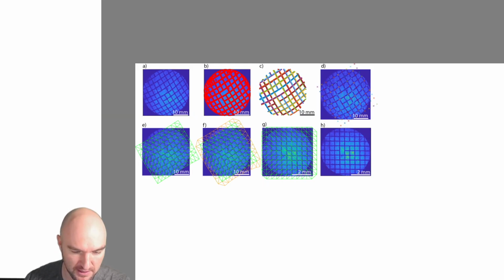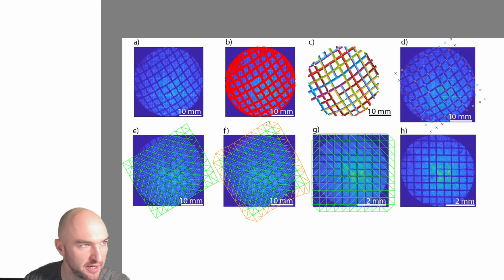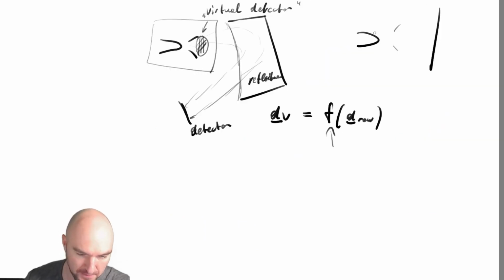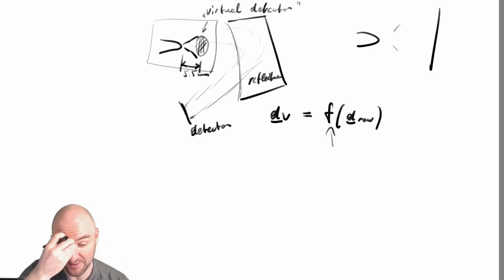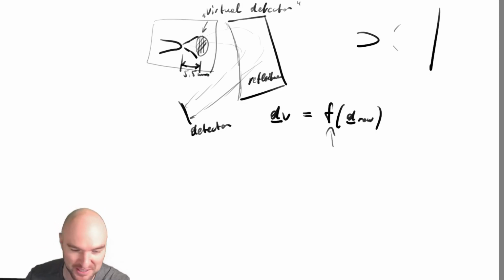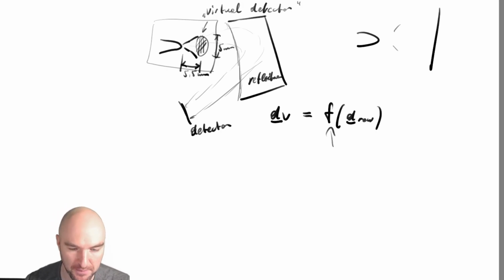In practice, how did that work? So in practice, we just created that grid and put it behind the local electrode. If you look at the local electrode, this is about 5.5 millimeters. I haven't determined it to the last digit of precision, so it might be 5, it might be 6, but there or thereabouts. And the diameter then is about 5 millimeter as well, at least for our atom probe.